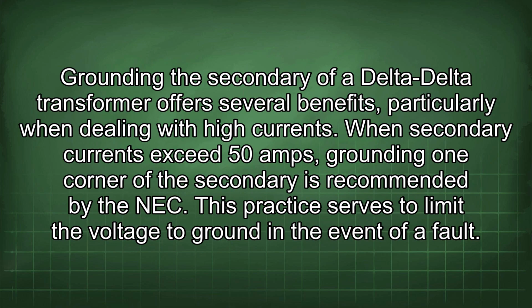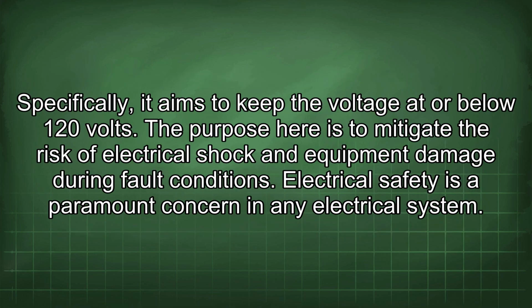Grounding the secondary of a delta-delta transformer offers several benefits, particularly when dealing with high currents. When secondary currents exceed 50 amps, grounding one corner of the secondary is recommended by the NEC. This practice serves to limit the voltage to ground in the event of a fault. Specifically, it aims to keep the voltage at or below 120 volts. The purpose here is to mitigate the risk of electrical shock and equipment damage during fault conditions.